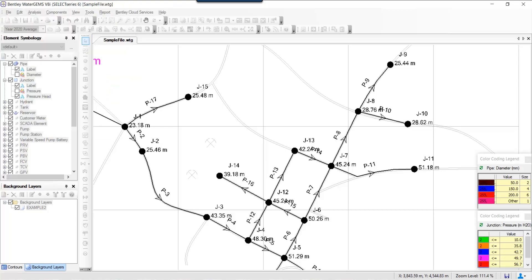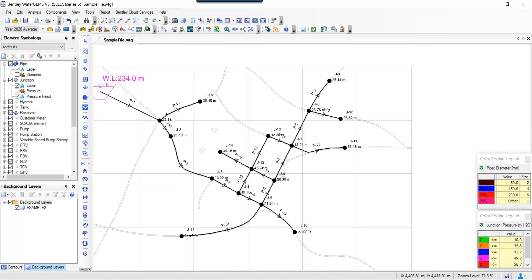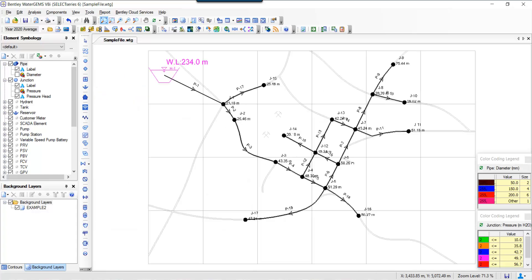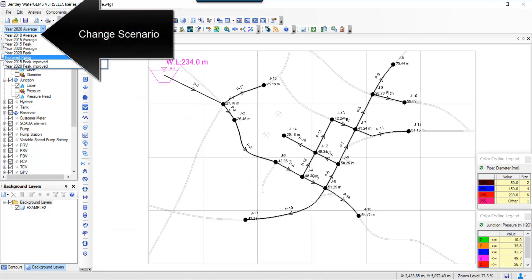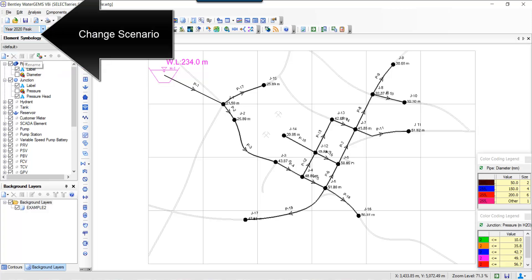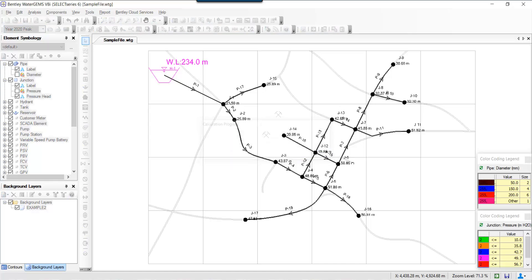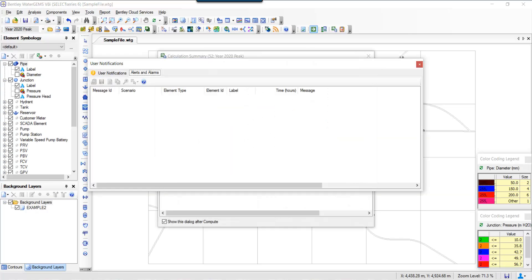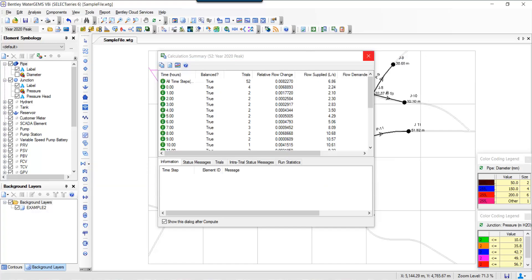Now once you do that, the next thing you could do is basically change scenario. So I did it for a 2020 average demand. Now I'm going to do it for a peak demand and recompute the model. You would see that there might be some issues—there are some alerts and the pressures are a little bit down at some point of time. So initially it's fine.